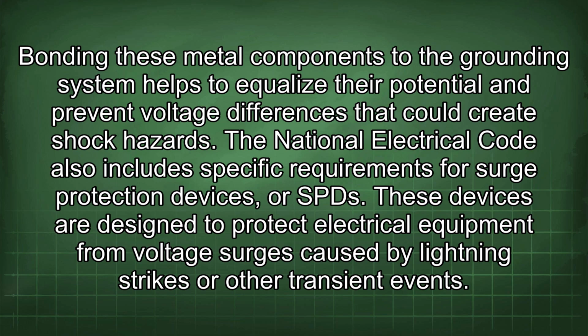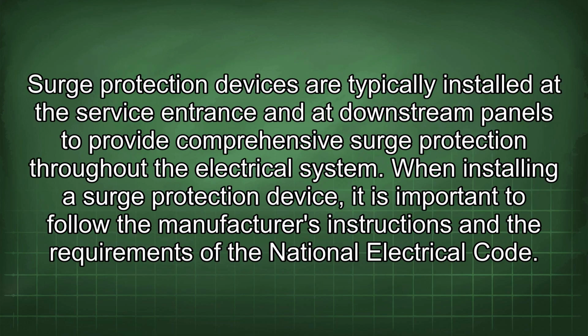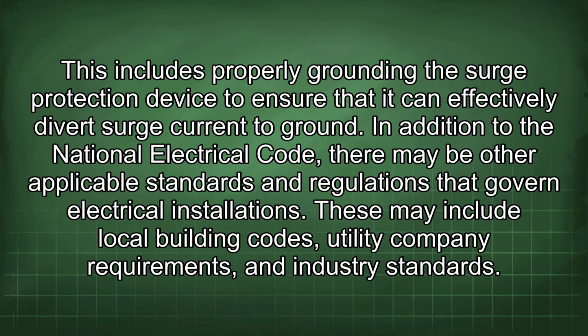These devices are designed to protect electrical equipment from voltage surges caused by lightning strikes or other transient events. Surge protection devices are typically installed at the service entrance and at downstream panels to provide comprehensive surge protection throughout the electrical system. When installing a surge protection device, it is important to follow the manufacturer's instructions and the requirements of the National Electrical Code. This includes properly grounding the surge protection device to ensure that it can effectively divert surge current to ground.